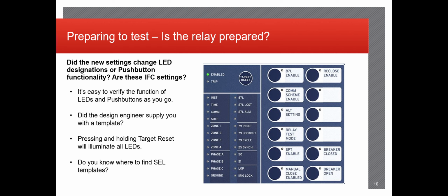the template that the design engineer gave you. Pressing the target reset button will always illuminate all LEDs and usually will reset them as well, unless there's a standing trip or standing fault on any of the relay logic. These SEL templates are usually provided by the design engineer, but sometimes they'll just give you a list of what labels should go where for the LEDs and push buttons.